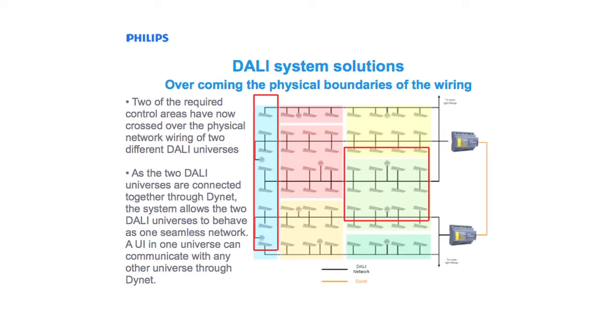When the DUS804C DALI sensor picks up motion within an area of the office, it will transmit a message back to the DALI load controller, which will then transmit the message back to Dynet. This message will be picked up by the adjacent load controller and will perform the appropriate action, so that the two lighting groups that you see here, which have crossed the physical DALI boundary, are operating as one. This allows for the entire Dynalite system to be indefinitely scalable, whether we need it to be one room, a tenancy, a floor, or an entire building. By using the Dynet system to communicate between the various Dynalite devices, practically any required function can be achieved.